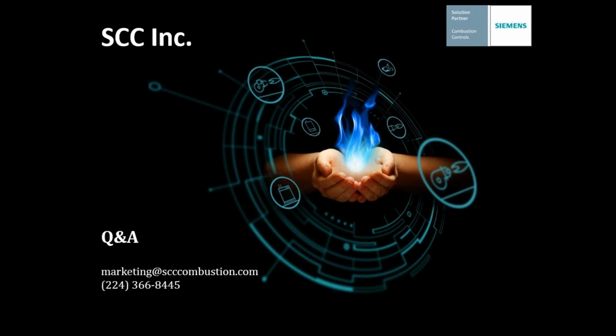And go for it, Dave. Take that and run with it if you would. LMV3, you can use it on a 5,000 horsepower burner if you want. That's a bit of an exaggeration. The limitation on the LMV3 is not horsepower. The limitation on the LMV3 is the torque required to move an actuator. I mean, an actuator device such as an air damper. Air dampers are usually the heaviest device on a burner.